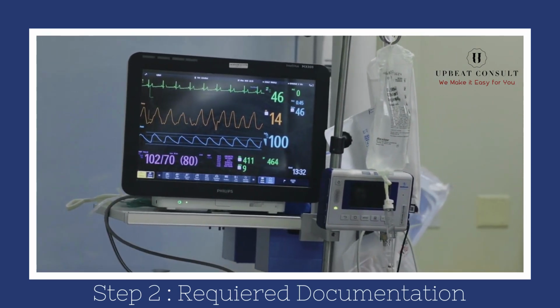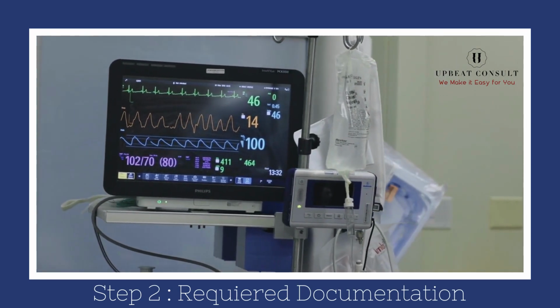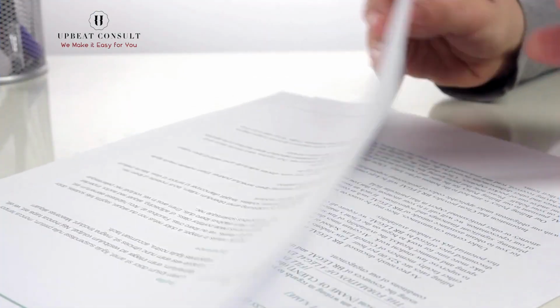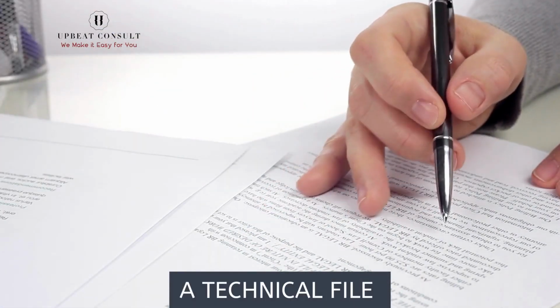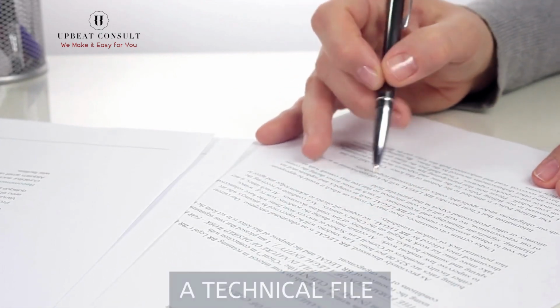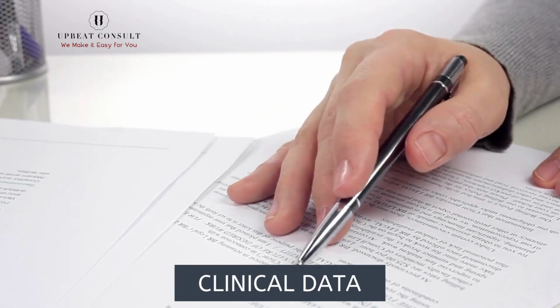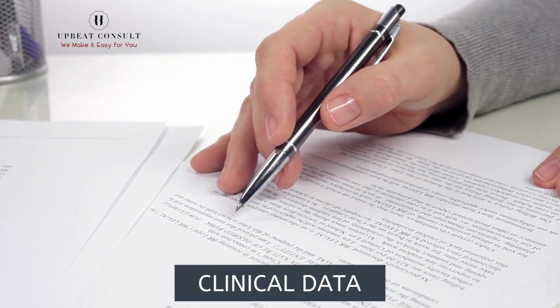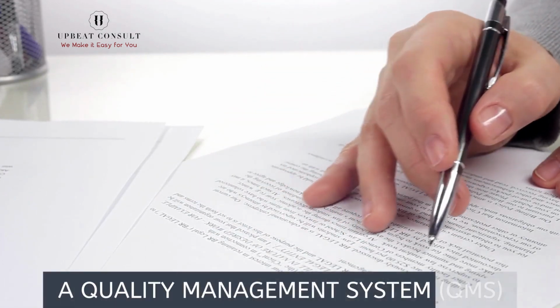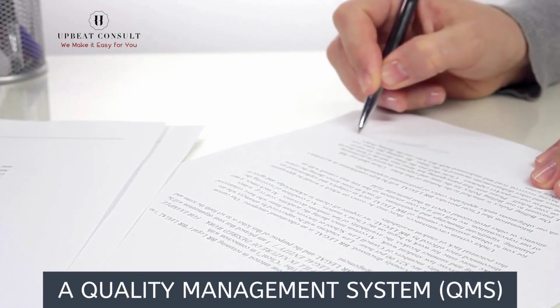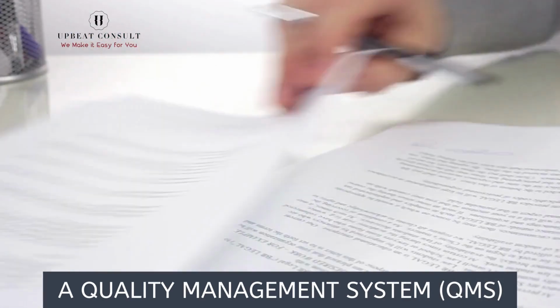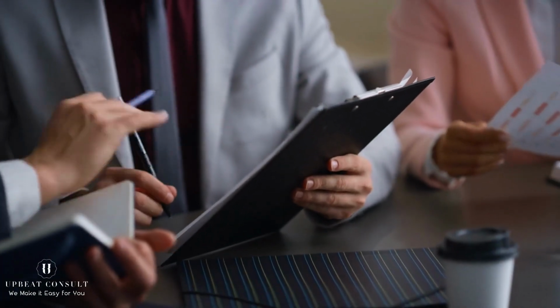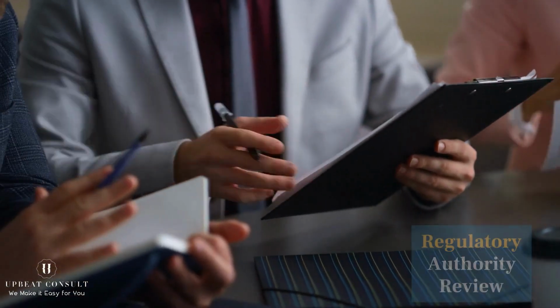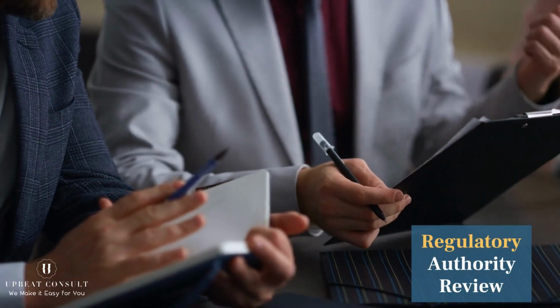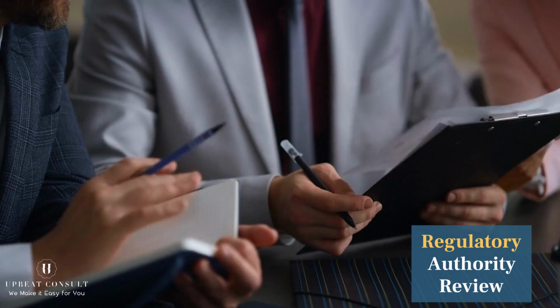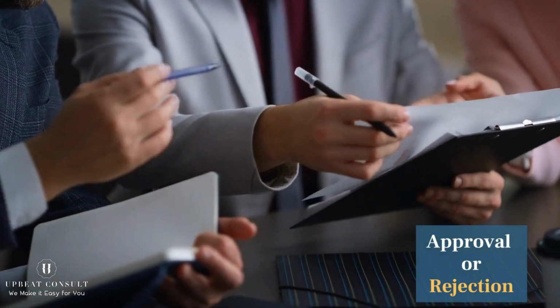The documentation required for registration will vary depending on the country, but it will typically include the following: a technical file that describes the design, manufacturing, and testing of the device. Clinical data that demonstrates the safety and effectiveness of the device. A quality management system, QMS, that ensures that the device is manufactured and tested to high standards. Once the documentation is complete, it is submitted to the regulatory authority for review. The regulatory authority will review the documentation and decide whether to grant registration to the device.